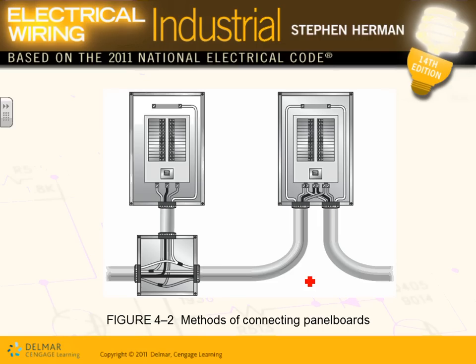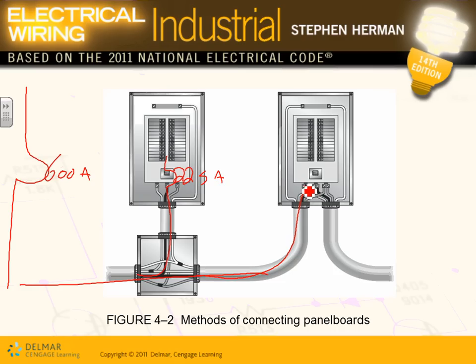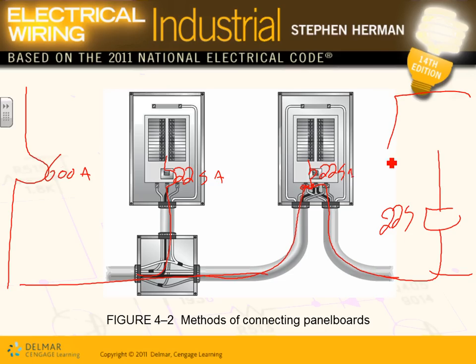Look at this feeder. I can have a feeder here, gentlemen, coming in here. And my feeder, let's just say this feeder was a 600 amp feeder. I can tap from this feeder in here and feed this panel, a 225 amp panel, through a junction box. And I can come over here, guys, through this connection and keep moving. Can you see that? Another 225 amp, and keep going to a third 225 amp, and as much as the feeder can handle.